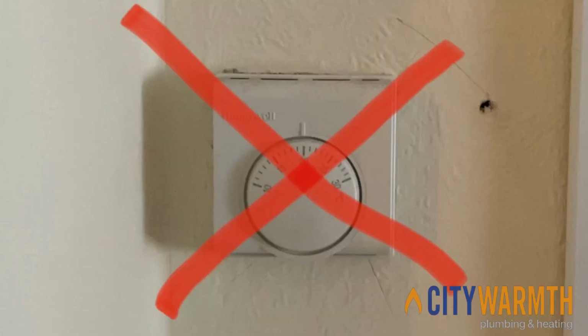So how far can we take this? If Martin Lewis and the UK government are recommending that the flow temperature should be 60 degrees, is that the number to go to? Well, no would be my short answer on that. Remember, we're talking about the boiler flow temperature here and not the temperature on your room thermostat. But if your boiler flow temperature is currently set to 70 degrees, 75 degrees, maybe even 80 degrees, reducing it to 60 degrees will save you a good amount of money on your gas.